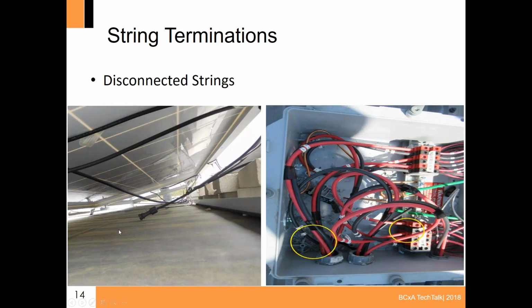Once in a while, a visual inspection will show that connectors were either unplugged or, more likely, they forgot to plug them in. The way these connectors work, you actually need a tool to open them or unplug them. So in this case, these installers might have just forgotten to make that connection. An open circuit voltage reading will show this most likely, and some other testing will show it as well. Again, we give it a visual, we could see that it's disconnected, but when we take voltage readings, we should see an outlier on this particular string. So that's another indication that this was not made up properly.